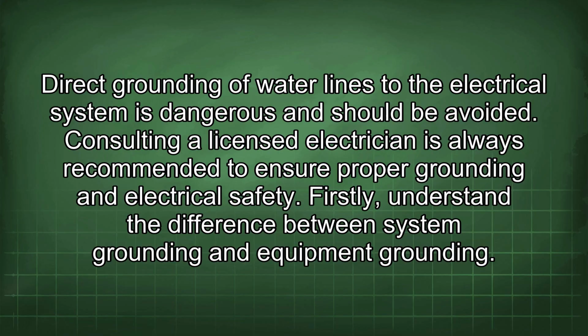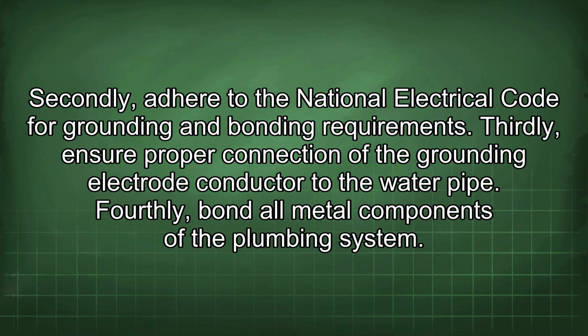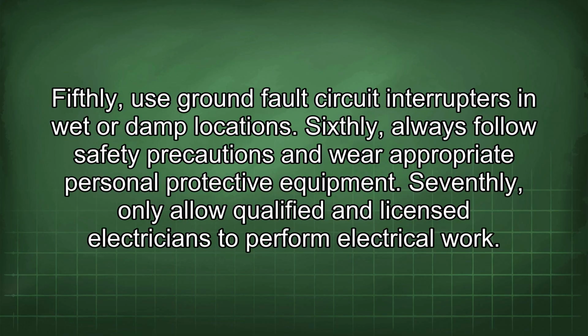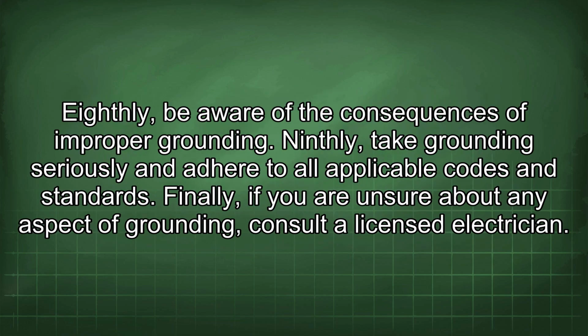Firstly, understand the difference between system grounding and equipment grounding. Secondly, adhere to the National Electrical Code for grounding and bonding requirements. Thirdly, ensure proper connection of the grounding electrode conductor to the water pipe. Fourthly, bond all metal components of the plumbing system. Fifthly, use ground fault circuit interrupters in wet or damp locations. Sixthly, always follow safety precautions and wear appropriate personal protective equipment. Seventhly, only allow qualified and licensed electricians to perform electrical work. Eighthly, be aware of the consequences of improper grounding. Ninthly, take grounding seriously and adhere to all applicable codes and standards. Finally, if you are unsure about any aspect of grounding, consult a licensed electrician.